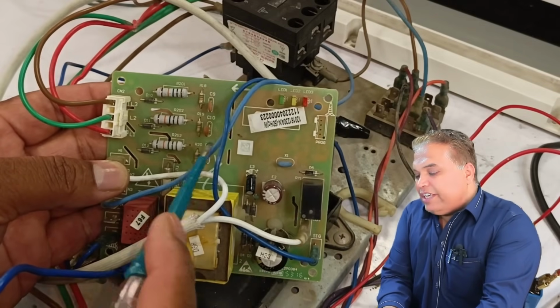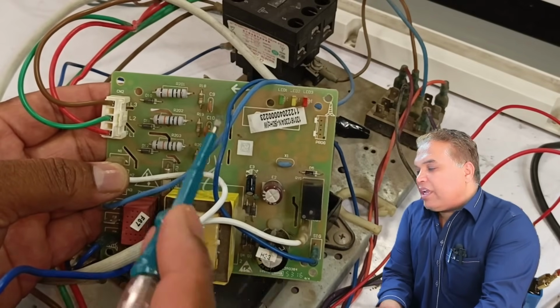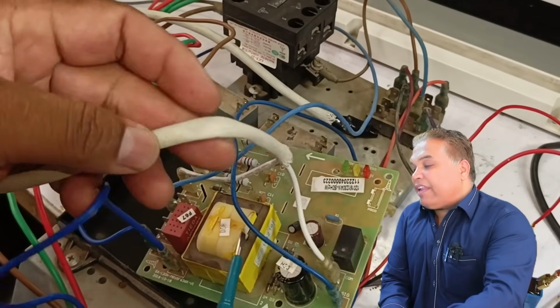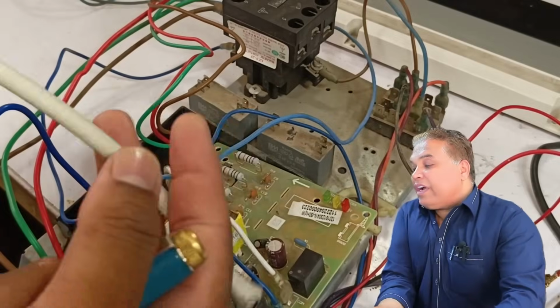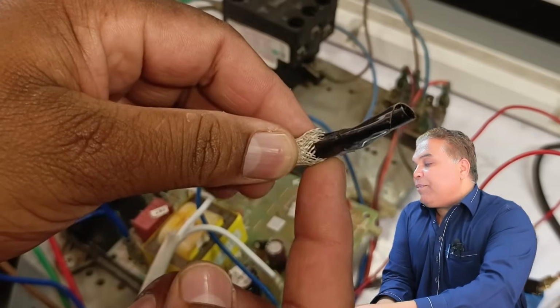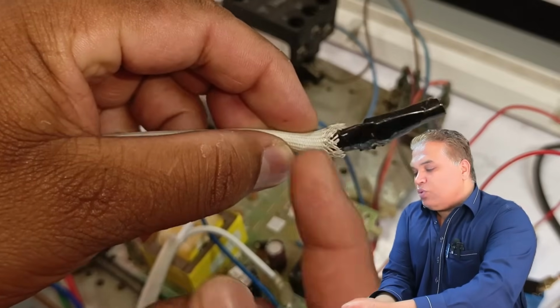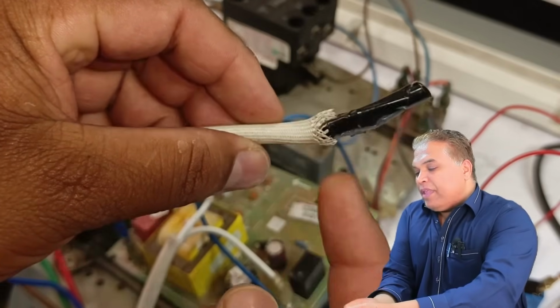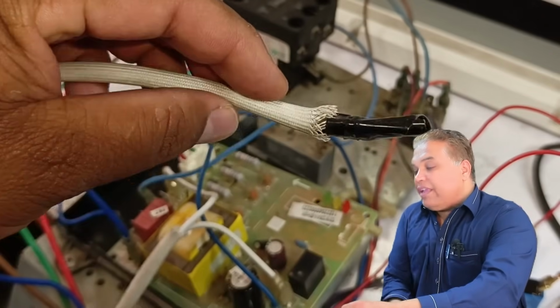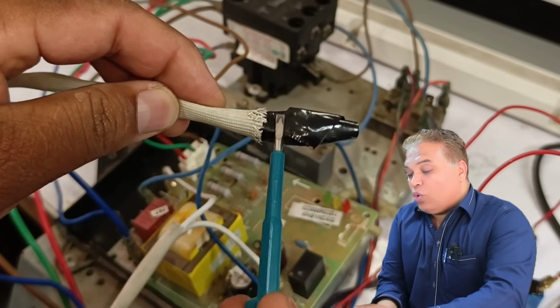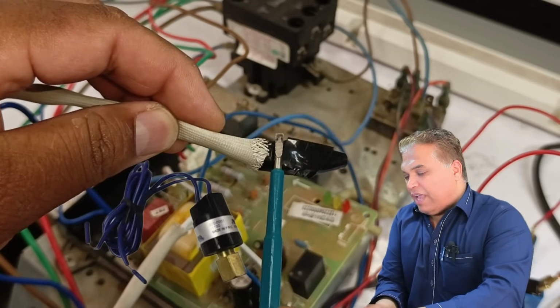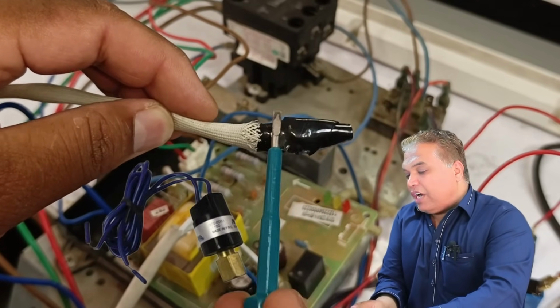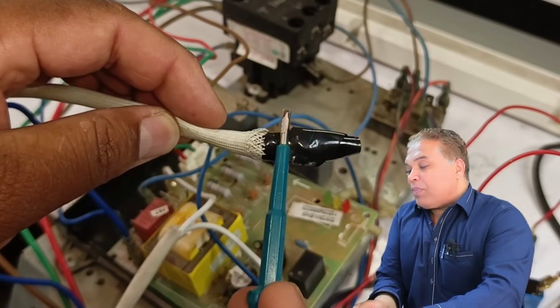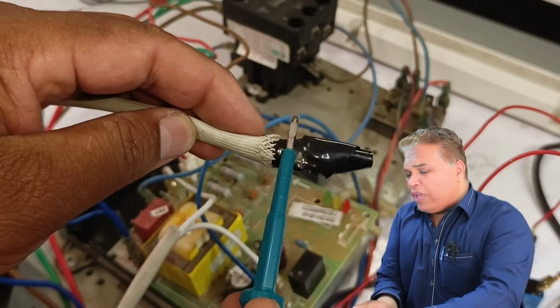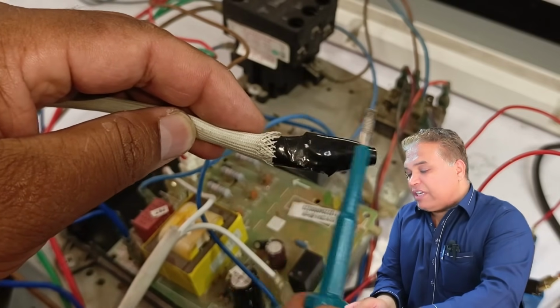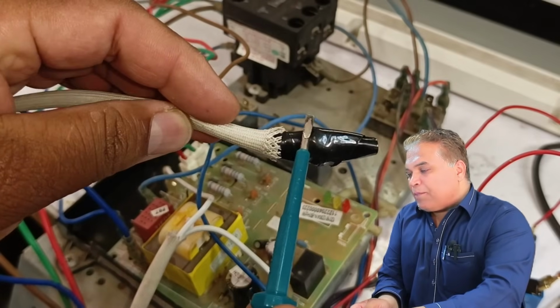Whether it's the phase detection signal or this control signal, you can see this white wire here. I have currently connected it in series, or you could say I've shorted it, so that I can proceed with the testing. This is because the high-pressure switch is not currently available in my setup. The high-pressure switch normally provides continuity, and when the pressure in the condenser rises too high, the switch turns off. When it turns off, the 2 wires disconnect from each other, and there will be no continuity. But as long as there is continuity, that means the outdoor unit is working properly, and there is no fault.